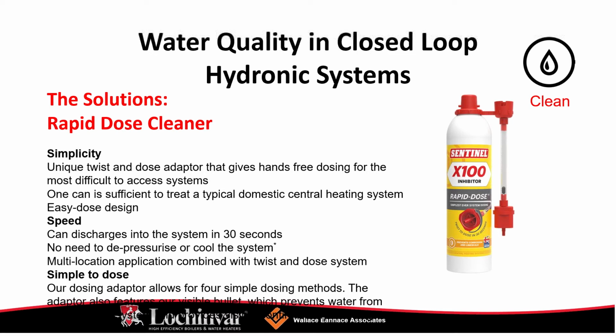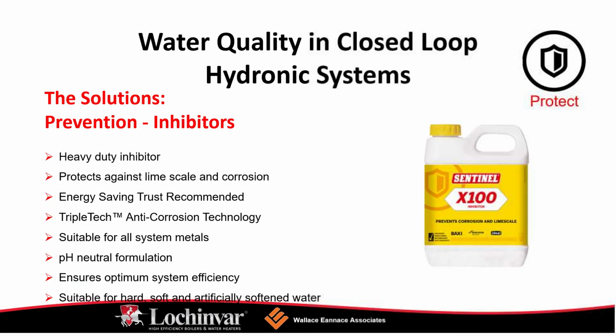System cleaner, Sentinel offers the X300. This is really for new heating systems, so new installs or new systems that are inside of 6 months old. This is ideal. Very powerful, heavy-duty cleaner. Removes installation debris. It washes off any kind of manufacturing greases. Eliminates corrosive flux residue. Again, all tying into maybe what you'd find typical after a new installation. And we prevent harmful copper deposits from being left in the system. And it's basically preparing the system for protection with the X100 inhibitor.